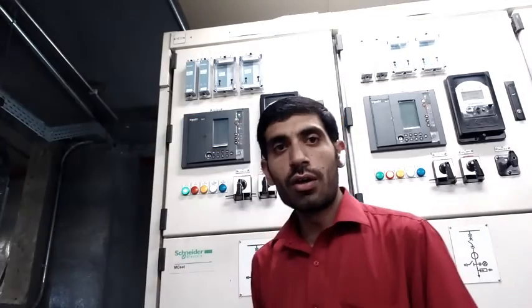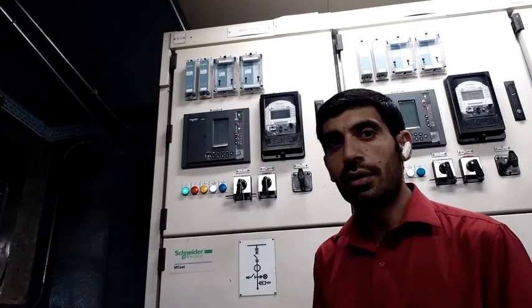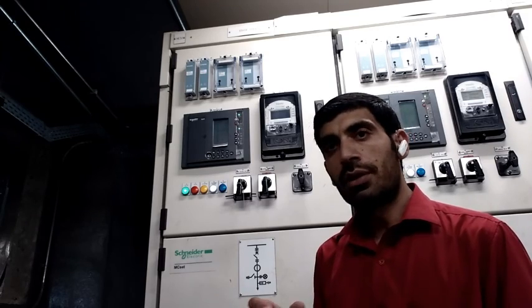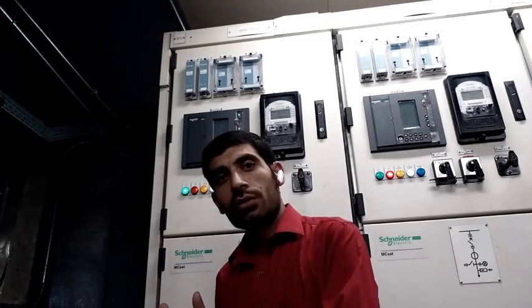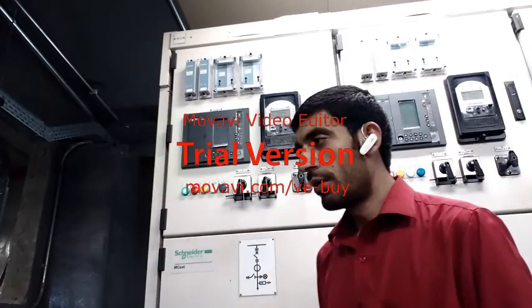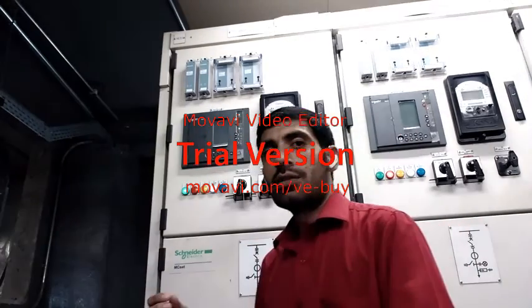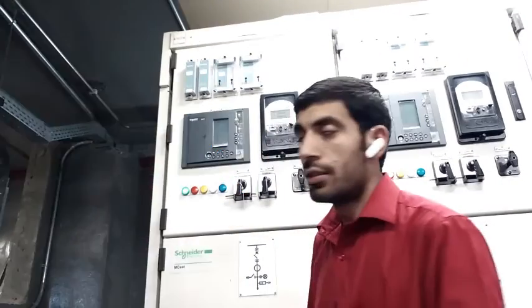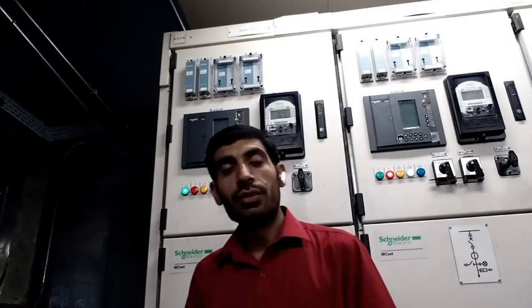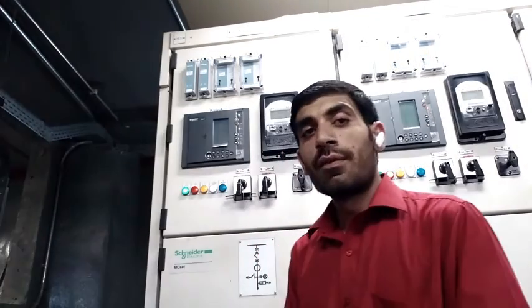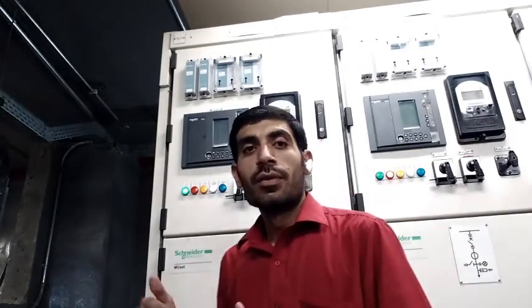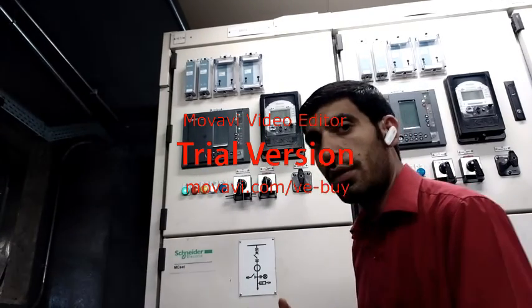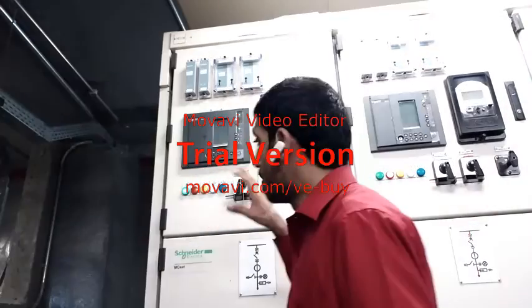If my earth fault cable CT senses 10 amperes on the primary side, for example if my cable is damaged or any phase is grounded, this CT will sense it, and when it reaches 10 amps it will give an alarm here, and this relay will be tripped within 200 milliseconds. This is a very short time, for the safety of this feeder, the persons, and the motor. This is for earth fault protection.